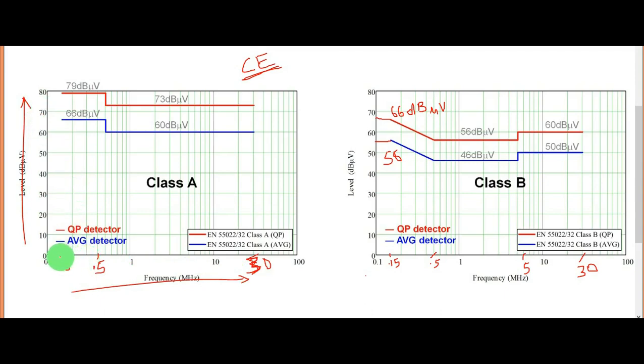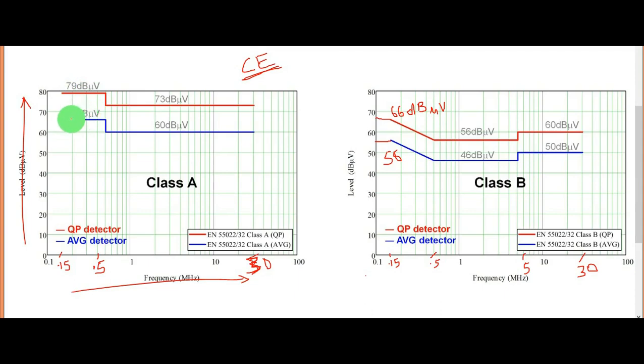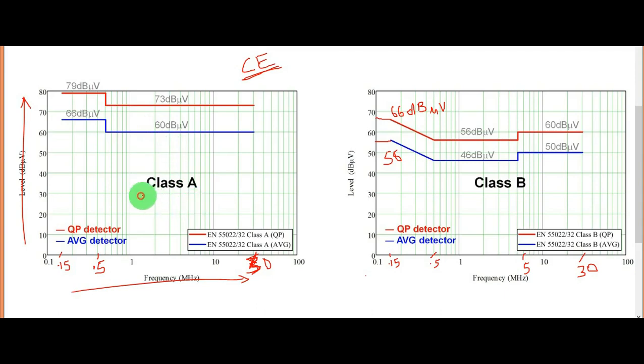Between the frequency 150 kilohertz to 500 kilohertz — that is 0.15 megahertz to 0.5 megahertz — your quasi-peak limit is 79 dB microvolt and your average peak limit is 66 dB microvolt. After that, from 500 kilohertz to 30 megahertz, your quasi-peak limit reduces to 73 dB microvolt and your average peak limit also reduces to 60 dB microvolt. This is for Class A.